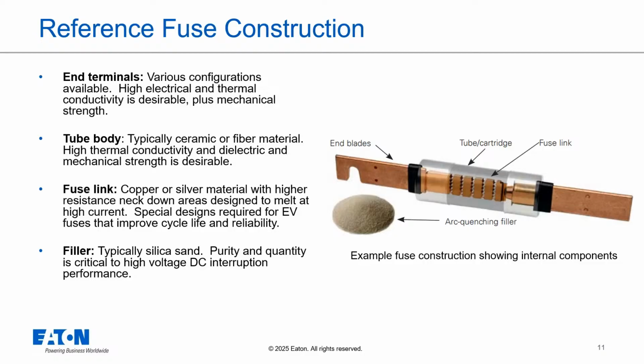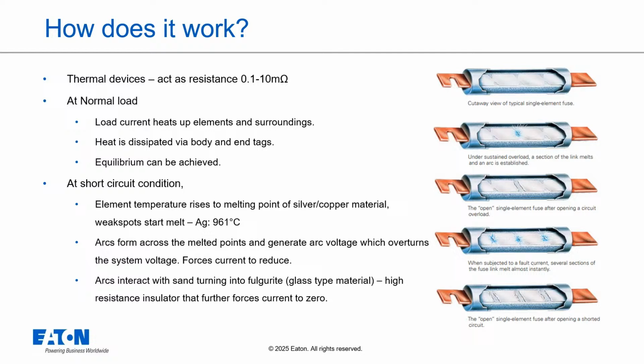So how does this all work? Fuses are thermal devices. They essentially act as a small resistance in the circuit. We're talking fractions of an ohm, like 0.1 to 10 milliohms. Under normal load conditions, current flows through the fuse link and it heats up slightly. This heat is dissipated through the body and the end terminals, and the fuse reaches a stable operating temperature.